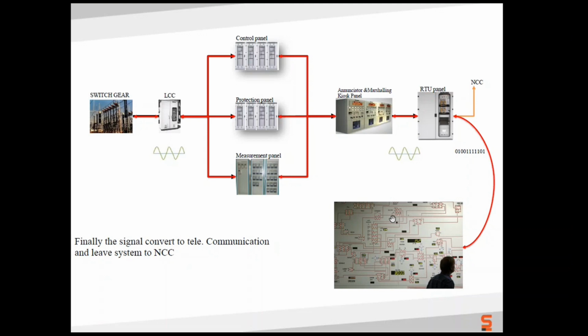So all this data comes to this RTU panel, and whatever data is required here, they require everything. Nowadays RLDC, the load dispatch center, wants the complete status of breaker, isolator, earth switch - everything - on its screen.